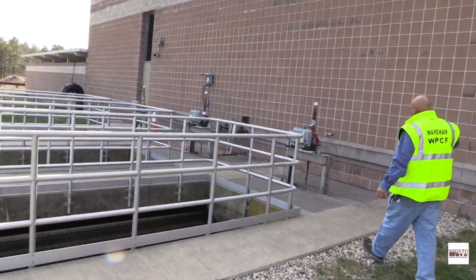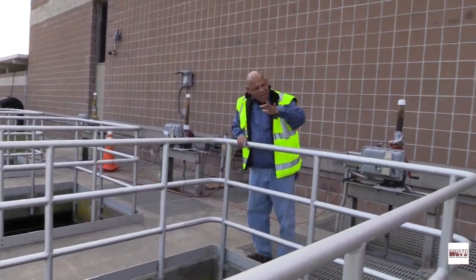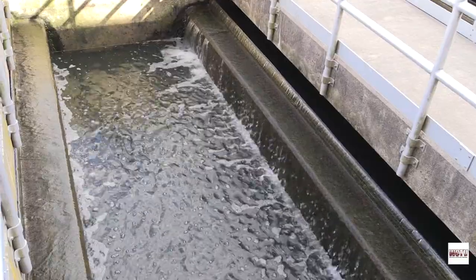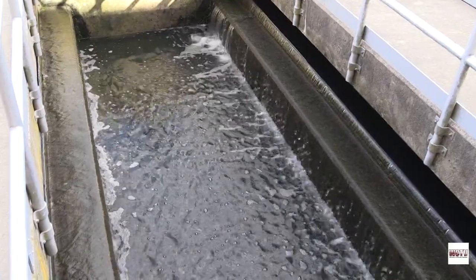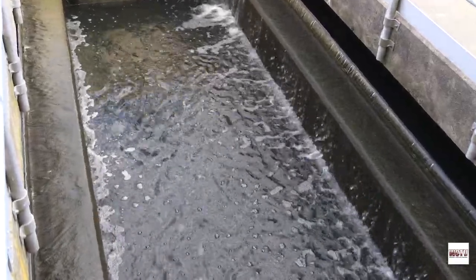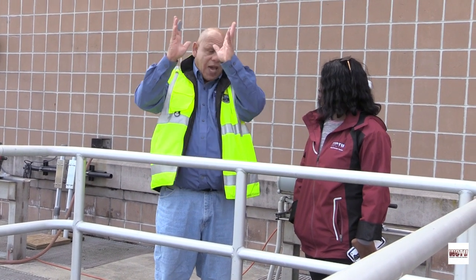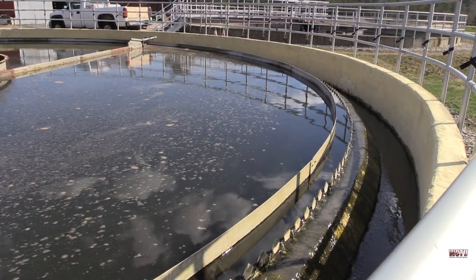And this is the sand filter. So it comes into each filter. We have three of them, and the water comes over, and then it goes down. There's a layer, I think about 3 feet, of rock, silica. They sit them together, and the water trickles through it. In the middle here is a biomass, and it's bacteria again. These bacteria are facultative, so they're chasing the element, the nitrogen. They strip off the nitrogen, and the nitrogen traps, and then this unit will come on every 3 hours, do a little bump, and release the nitrogen, and it goes into the atmosphere. This is the polishing.